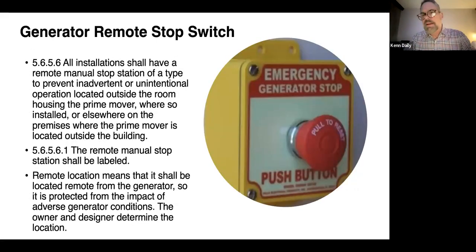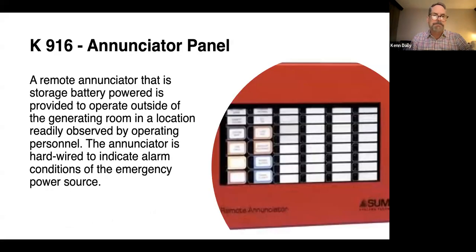One common citation across America is making sure you have a remote stop button for the generator. It can't be on the generator itself; it must be remote from the generator. I can't tell you whether it's 10 feet or 20 feet. It's not inside the fenced area, let's put it that way. It's outside, on a post or a wall. It has a sign, remote stop. Obviously, in some cases, you would not want the generator running during a fire or maybe even causing problems at the building, so you would have an emergency or remote stop button for that generator. This is expensive. It's a couple thousand, $3,000 to $4,000 to install an additional remote stop button.